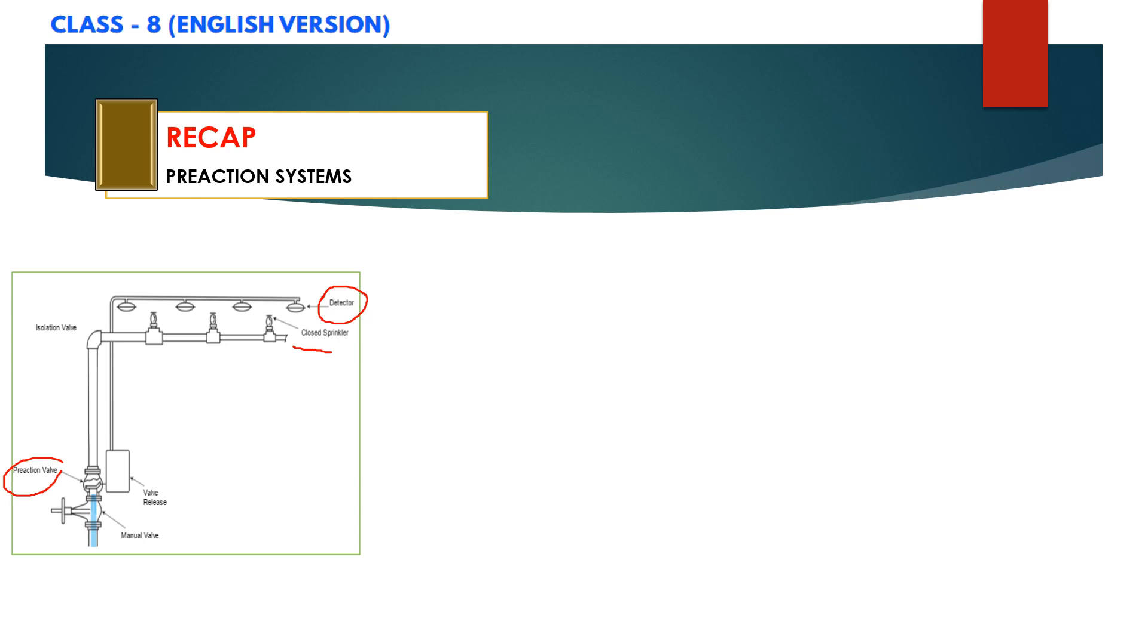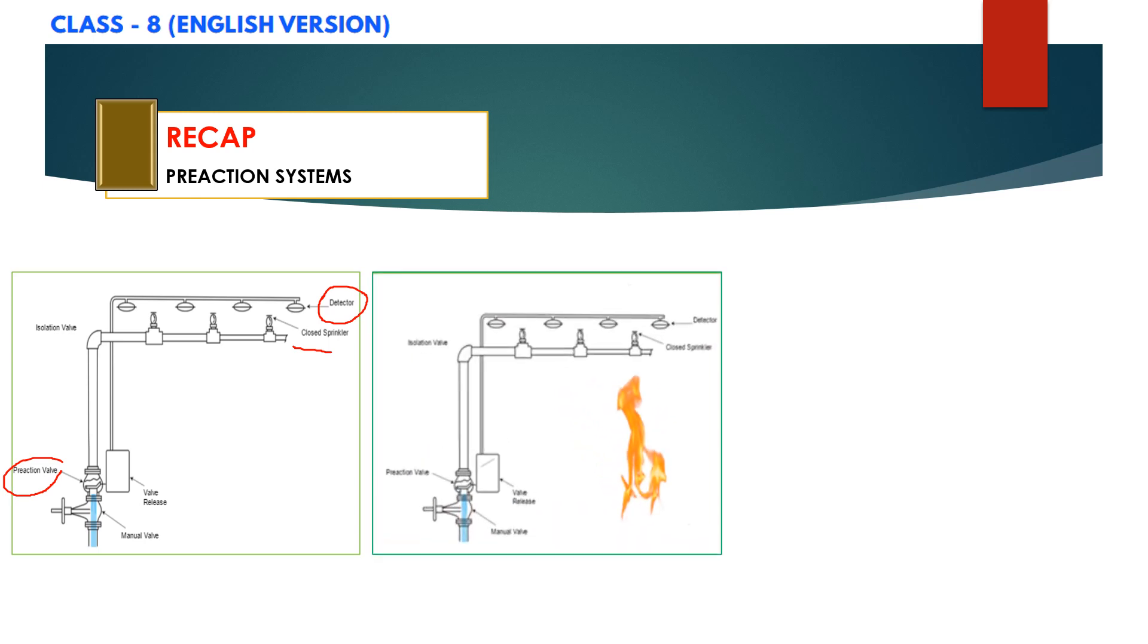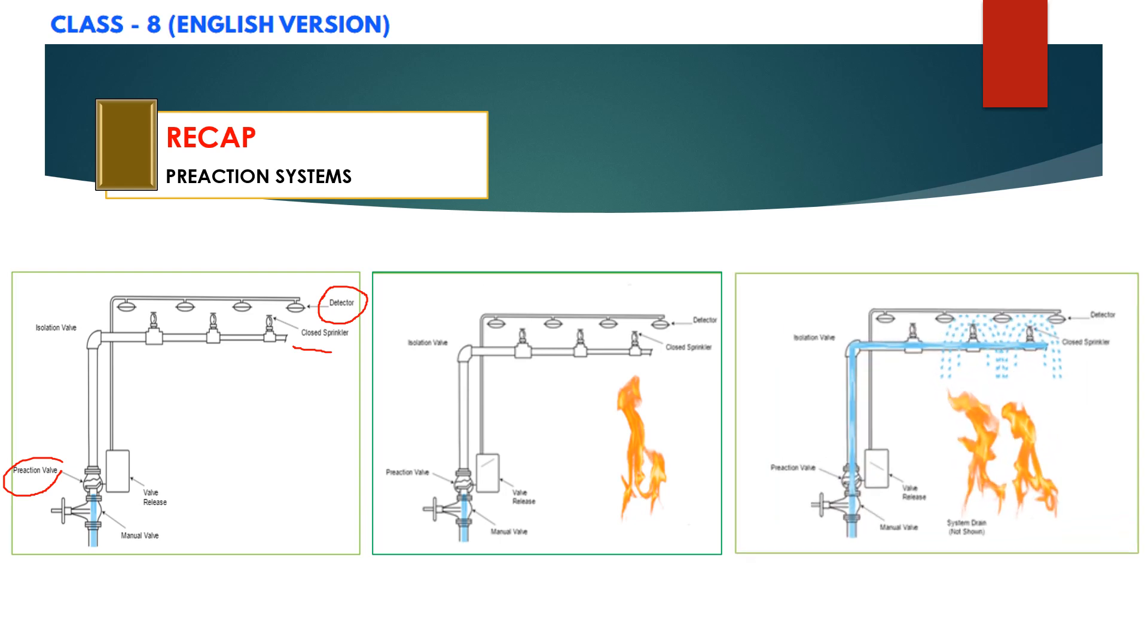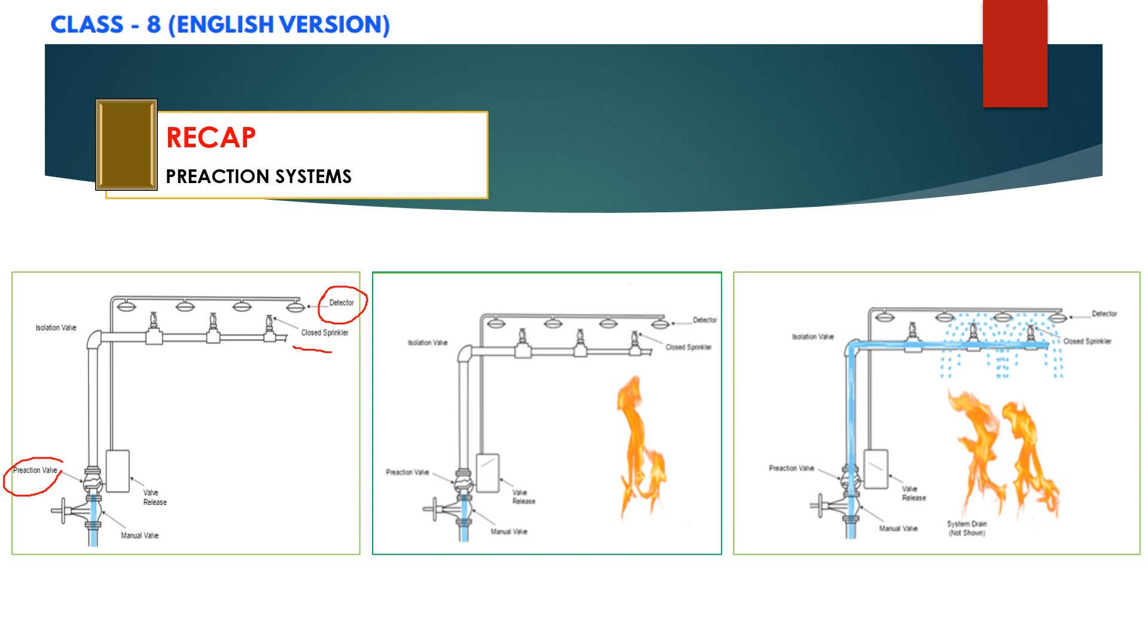All the sprinklers are normally closed and normally there is no water in the piping. When fire occurs, a supplemental detection system senses the fire and automatically opens the preaction valve. When the preaction valve opens, water will flow into the piping system. Water discharge occurs from each individual sprinkler as they fuse in response to heat.